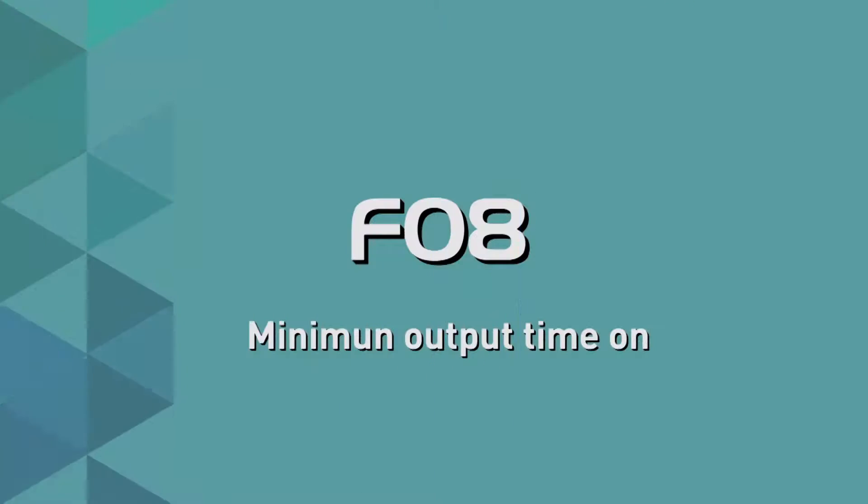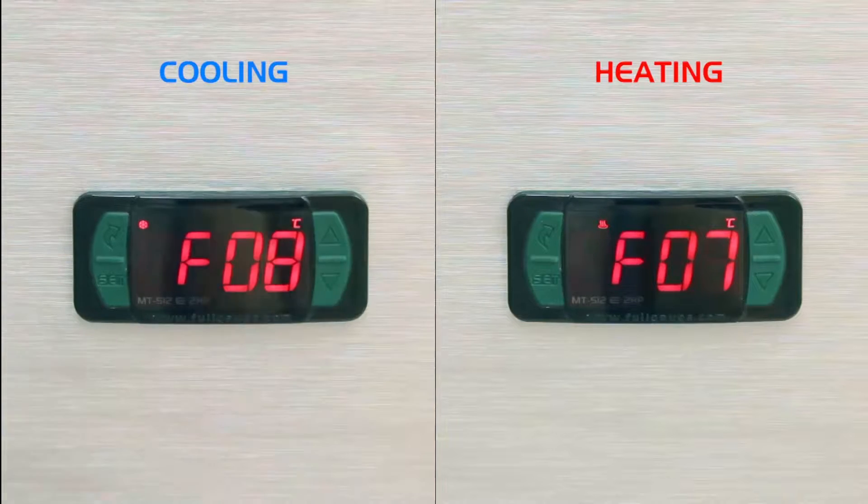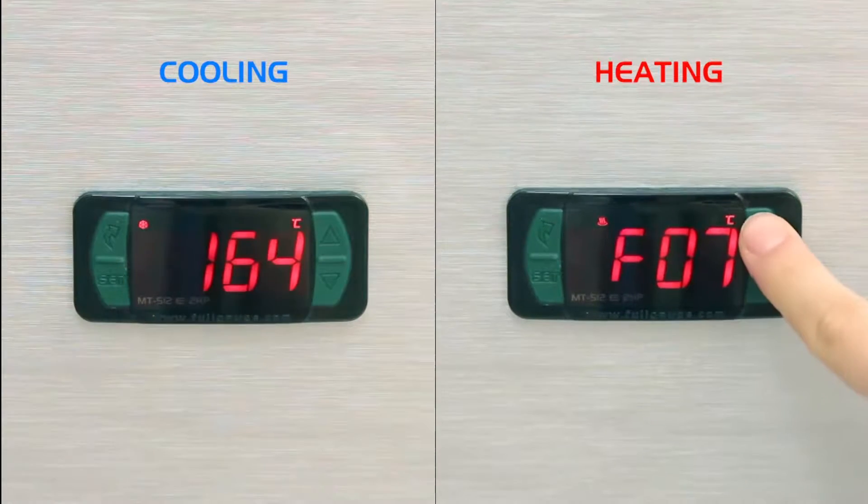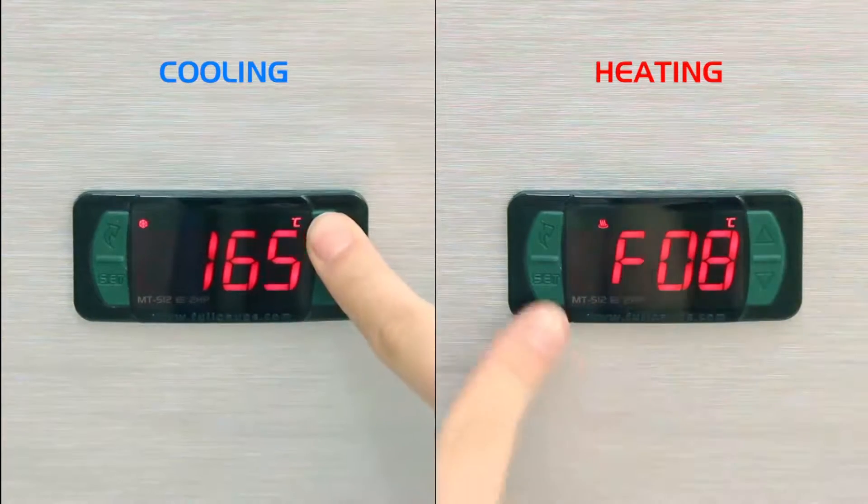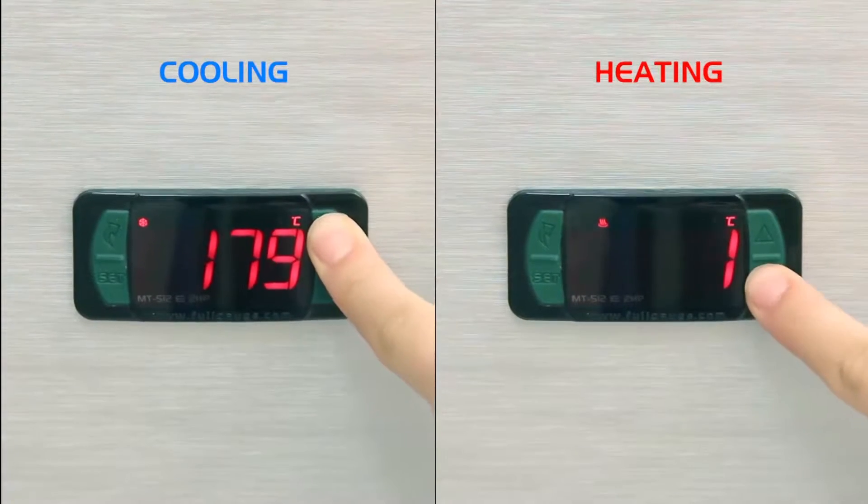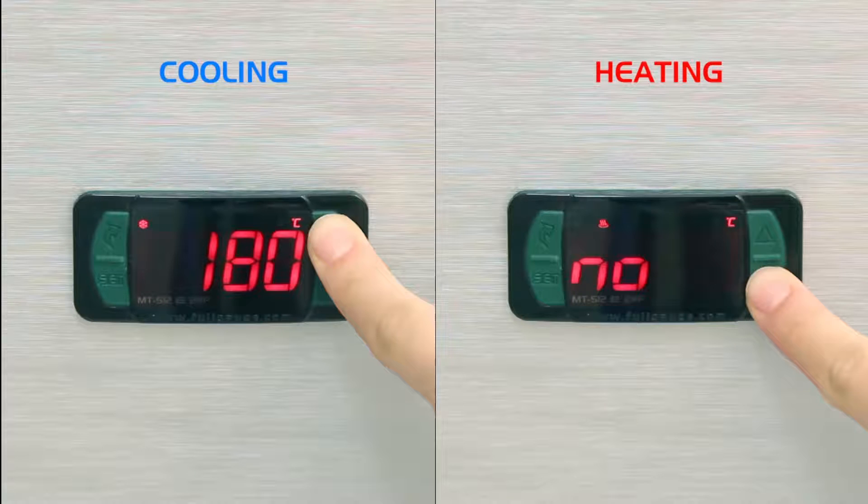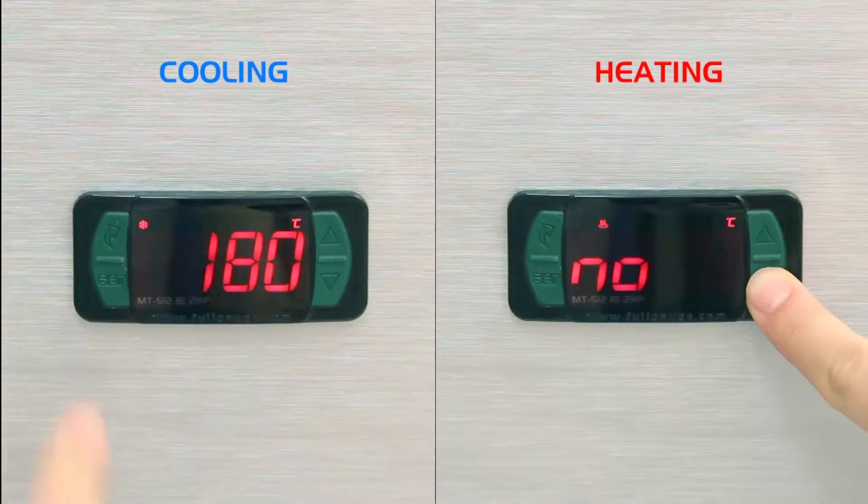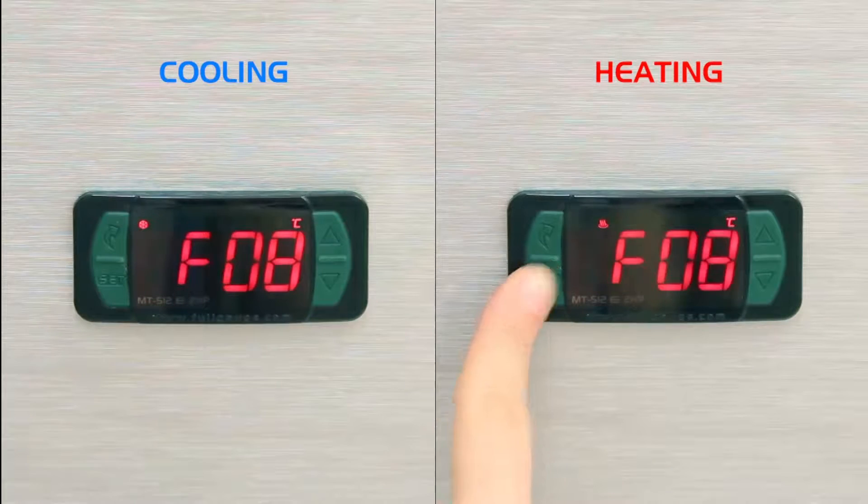F08, Minimum Output On Time. It is the minimum time in which the controller relay remains on after the last start. The goal is to avoid repetitive disconnections. In the cooling example, we opted for 180 seconds, and in the case of heating, we did not adopt a minimum time, selecting the No symbol.